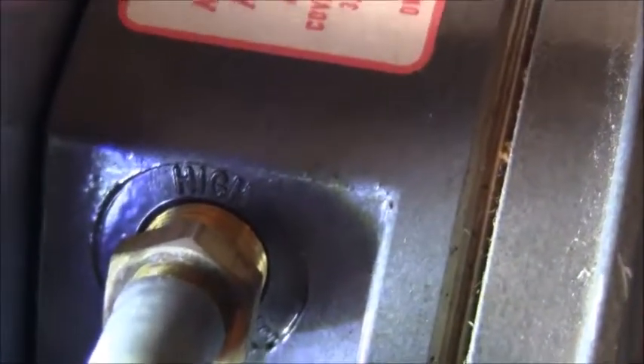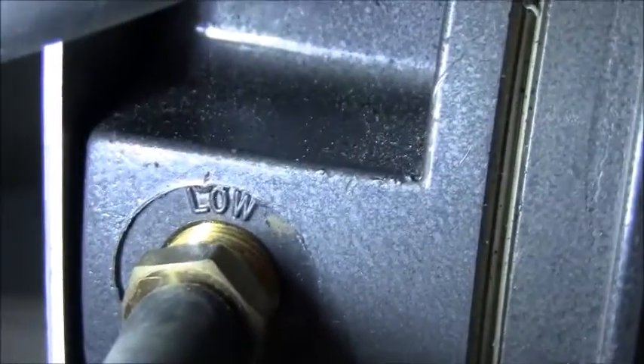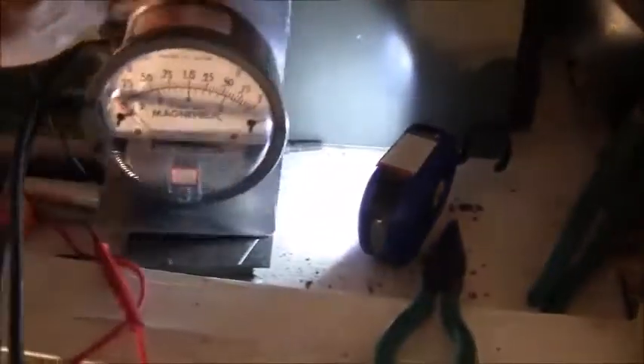Now remember, when you're looking at the Magnehelic gauge, there's two readings: the high and the low. The high is on the top, the low is on the bottom. So I'm going to go to the low setting. This one here you can see is the high, and the one underneath that is the low. Because this is below atmospheric pressure, I want the low. So the low is going to be the bottom tap, and I'm going to make sure my needle is on the low.